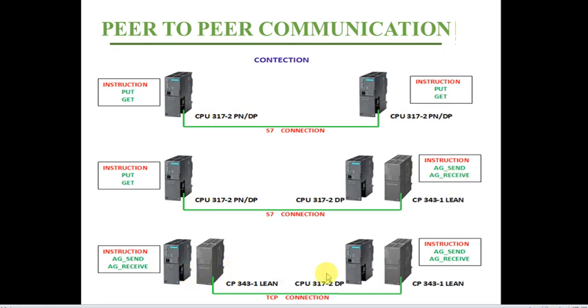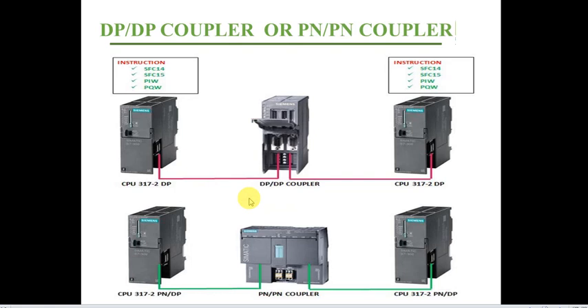The third layout is where neither PLC has a Profinet port, so we use a communication processor module on both sides to share data. The instructions used are AG_SEND and AG_RECV for both sides, and the connection type is TCP.